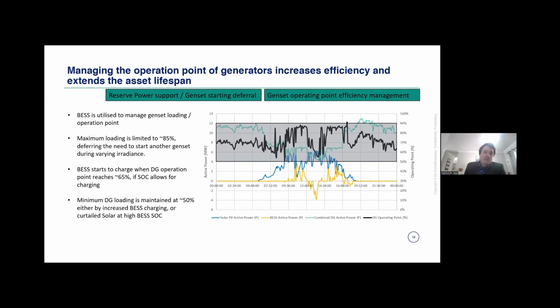So what we ended up implementing was essentially a maximum loading limitation on the gensets, which we set to about 85% of the nominal capacity of the generators. And by implementing this functionality, we were able to defer starting of additional gensets during the day. So I don't know if you can see my cursor here, but essentially if we look at conditions at about 10 o'clock here, we could see the solar PV. I chose a day that was very intermittent in terms of irradiation. Solar PV dipped by about 4 megawatt, and our gensets had to take up some of the additional capacity, and the battery immediately responded, injecting about 4 megawatts to ensure that the loading of the gensets does not exceed 85%, which allowed us to ride through that intermittent portion of the day.